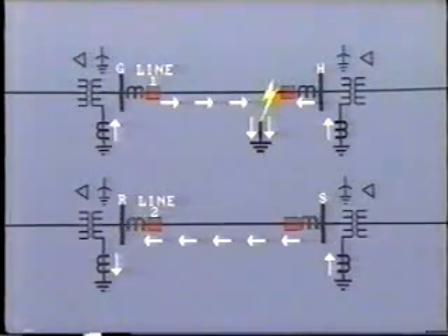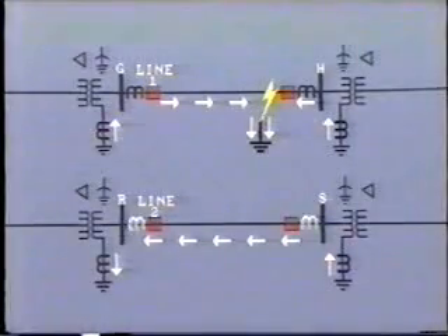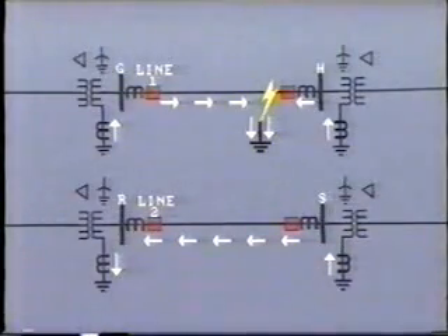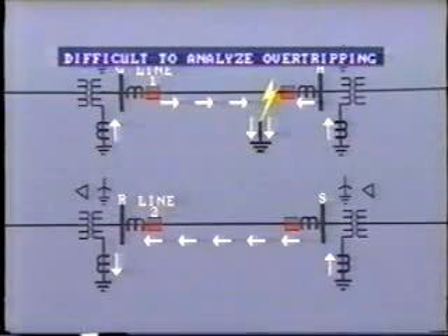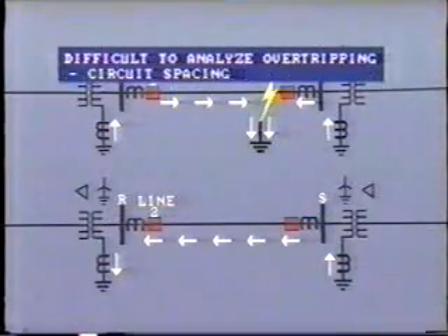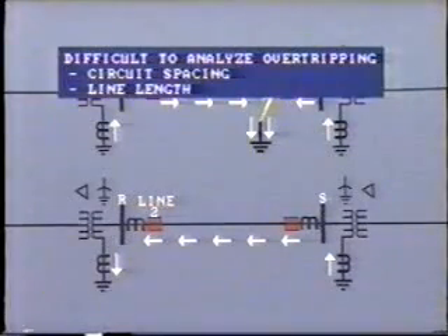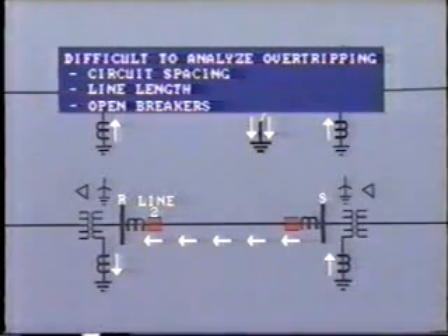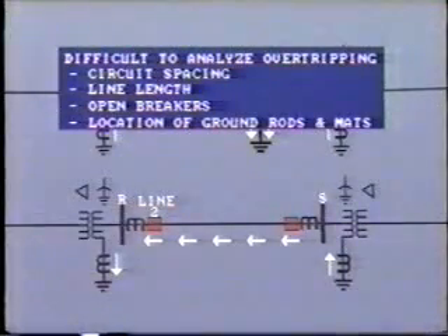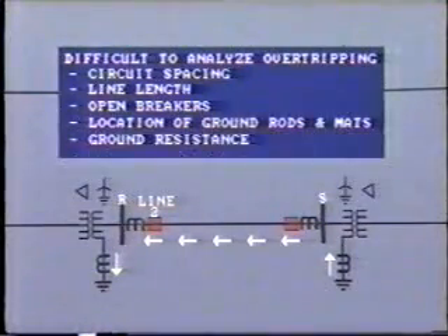Therefore, the two breakers on this line may be tripped quite incorrectly because of a fault on the other line. The problem of over-tripping due to mutual induction is difficult to analyze. In any situation, many factors, including circuit spacing, line length, open breakers, and so on, must be considered. The location of grounding rods and mats, as well as ground resistance, is also involved.